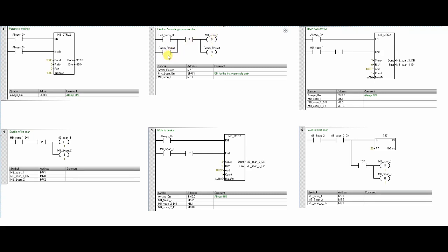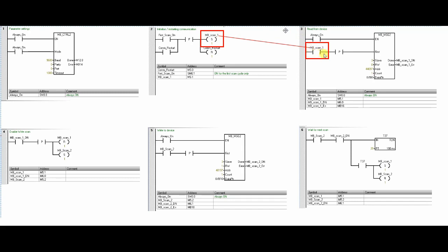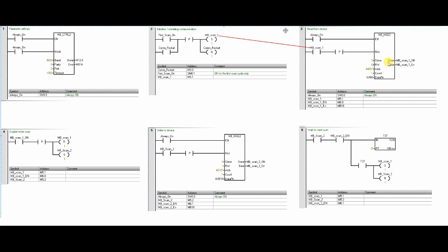Once the MB_Scan_1 bit is set, it will give a pulse to the MB_Message block in step number 3. Here I have configured the Modbus slave ID, address from which I want to read, and the pointer to the V memory where the data will be saved. Here PID's process value will be saved on the VW0.